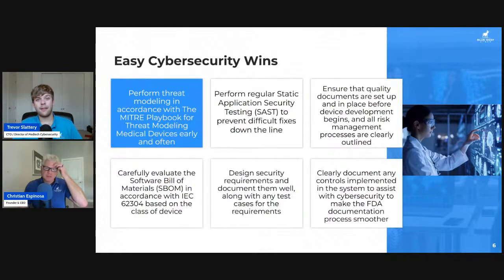All right. Now, I know we talked about this a little bit more before as well, but it's very important to design security requirements early and document them well. Once these are well documented, we also have to have the test case to verify it. Again, this is an FDA requirement. Security requirement test cases are required as part of that security testing documentation that the FDA wants. Security testing can be a little bit of an ambiguous term, but in general, it means static testing, requirement testing, penetration testing, fuzz testing, vulnerability assessment. There's a lot that it covers. And so this is just one area that we need to make sure we're covering. This is one of the more common areas that I see manufacturers forget about or leave to the very end, and it's very difficult to retrofit requirements onto a product.